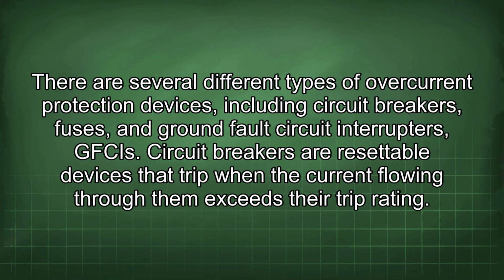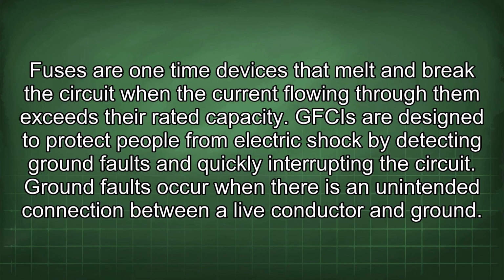appliances. There are several different types of overcurrent protection devices, including circuit breakers, fuses, and ground fault circuit interrupters, GFCIs. Circuit breakers are resettable devices that trip when the current flowing through them exceeds their trip rating. Fuses are one-time devices that melt and break the circuit when the current flowing through them exceeds their rated capacity. GFCIs are designed to protect people from electric shock by detecting ground faults and quickly interrupting the circuit. Ground faults occur when there is an unintended connection between a live conductor and ground.